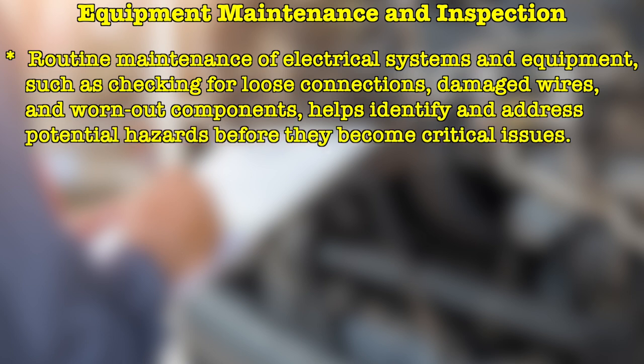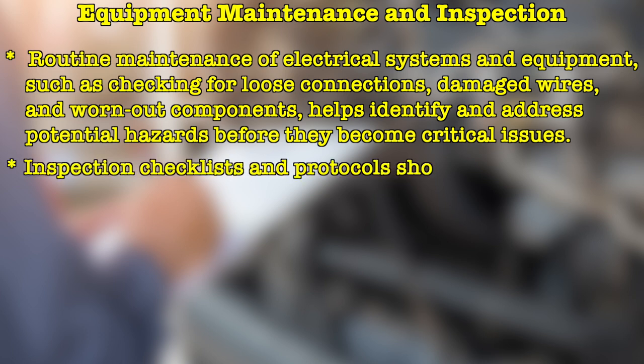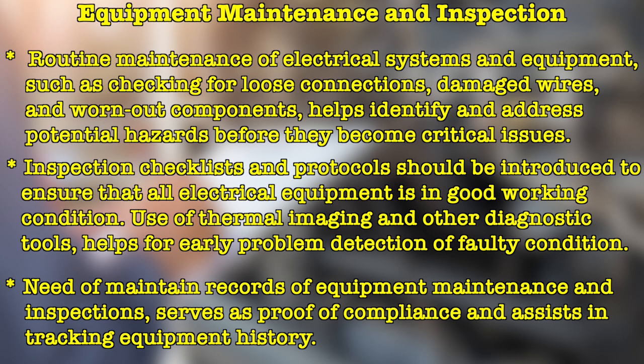Routine maintenance of electrical systems and equipment — such as checking for loose connections, damaged wires and worn-out components — helps identify and address potential hazards before they become critical issues. Inspection checklists and protocols should be introduced to ensure all electrical equipment is in good working condition. Use of thermal imaging and other diagnostic tools helps for early detection of faults. Records of equipment maintenance and inspections serve as proof of compliance and assist in tracking equipment history.